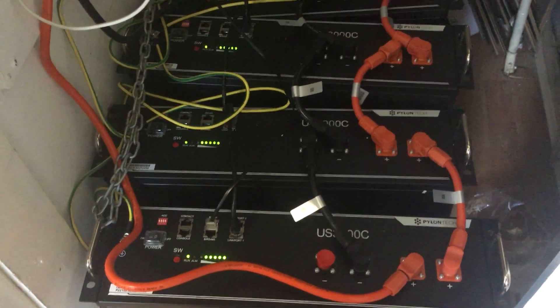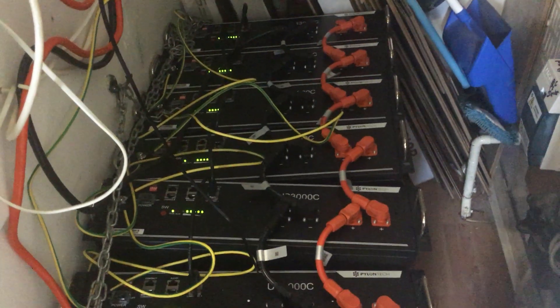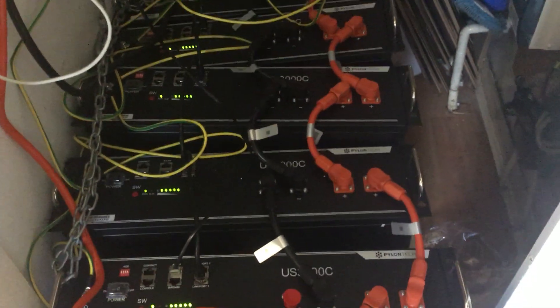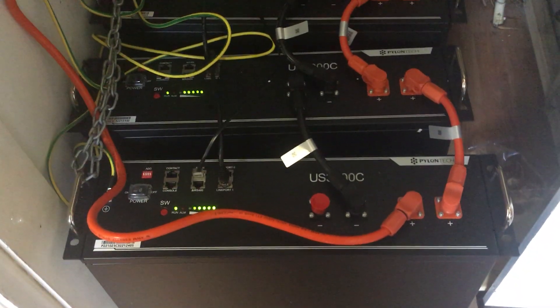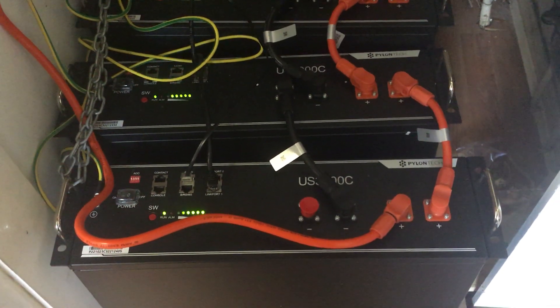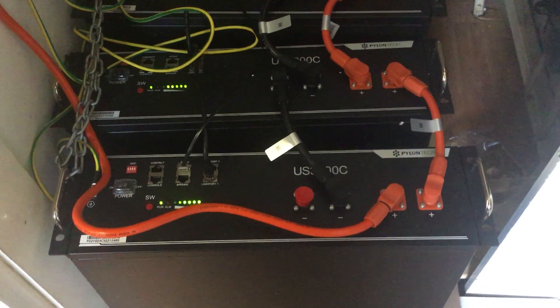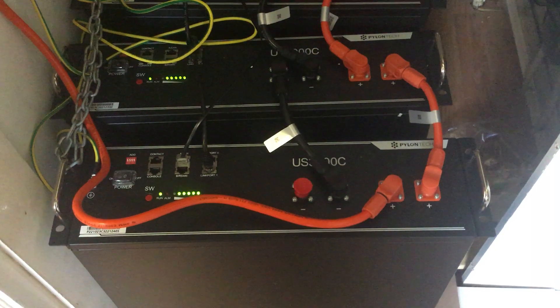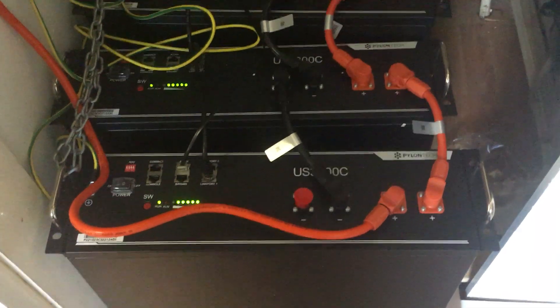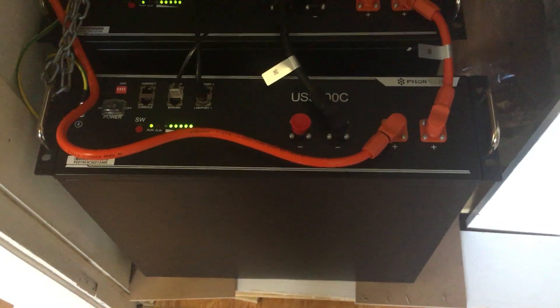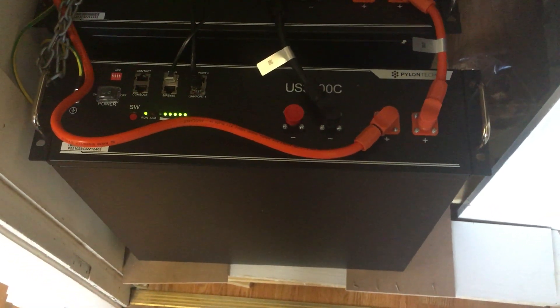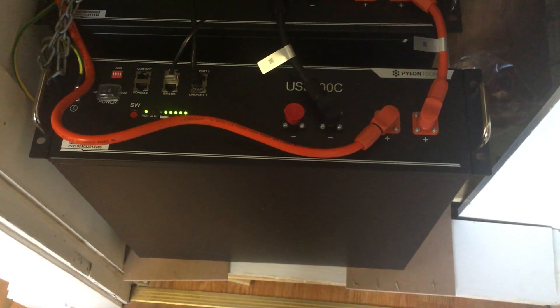Make sure all your network connections are okay, so zero to one, zero to one, zero to one. If you watch my earlier videos you'll see that's the way you network all the batteries up, even when you're adding a new one. So your last master battery, which is going to be this one here, you always leave link port zero free. So that tells the inverter that the last battery, which this is where we're pointing to now, is a master battery. Now this particular master battery has something called a BMS built into it. Some patterns of batteries will not have a BMS, they'll have a separate BMS, whereas these ones have it built in on each battery.